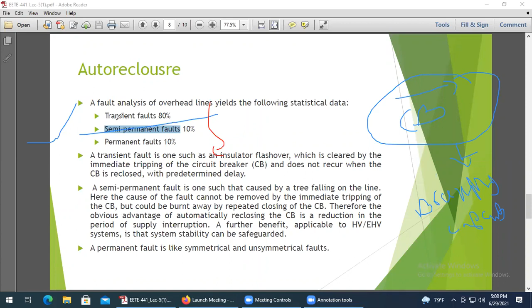But if you think about an auto recloser, due to a fault it is open, and with the presence of the fault, it will try to close again. Now, whenever it tries to close, the heat produced across the contact space of the circuit breaker is not equivalent to the breaking current. In fact, it is equivalent to the making current, the peak current. Okay. So that's why the capacity of the auto recloser is determined in terms of making capacity rather than breaking capacity, as it has to deal with the making current during interruption of the fault.